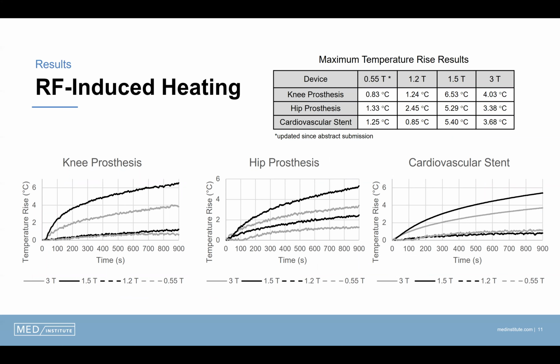All maximum temperature rise results were scaled to a whole phantom SAR of 2.0 watts per kilogram, besides for the 0.55 Tesla results, since experimental measurements indicated that the RF amplifiers are not capable of achieving a whole phantom SAR of more than 0.45 watts per kilogram. Comparison of the maximum temperature rises and of the temperature time plots for each device show that low field strength systems are able to reduce RF-induced heating for devices. For all devices, the low field strength scanners had the lowest heating, and the maximum temperature rises were typically significantly lower than for the higher field strength scanners.